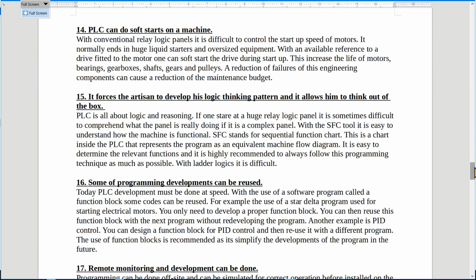Also, 14, what is important, is that a PLC can do soft starts on the machine. With normal relay logic panels, it's difficult to control the startup speed of motors. In the old days, we actually used more DC motors with huge liquid starters and oversized equipment. And the use of DC motors brought its own challenges. Later, we introduced inductors in line and startup of inductors, but it's not really practical, and it does take up a lot of space.